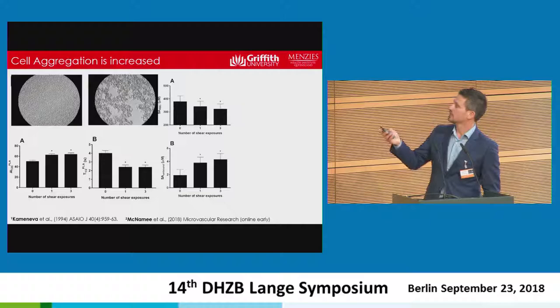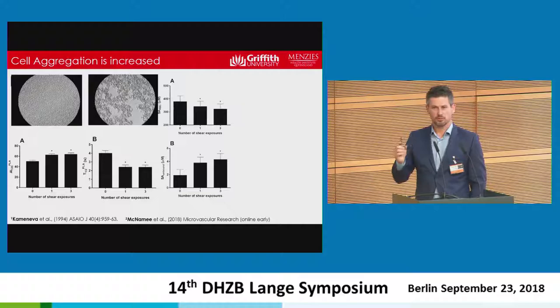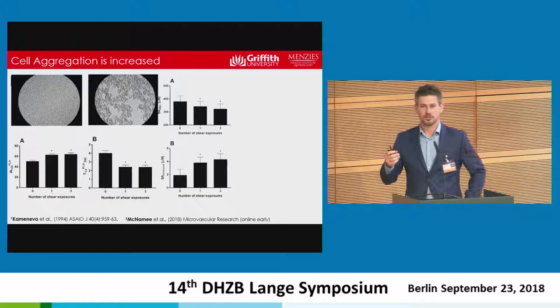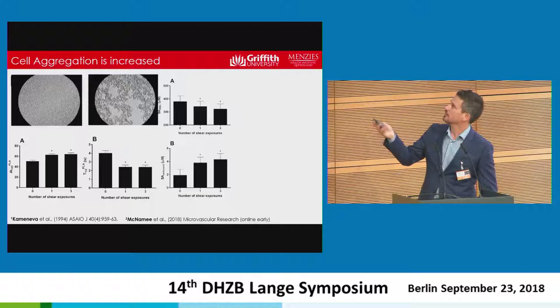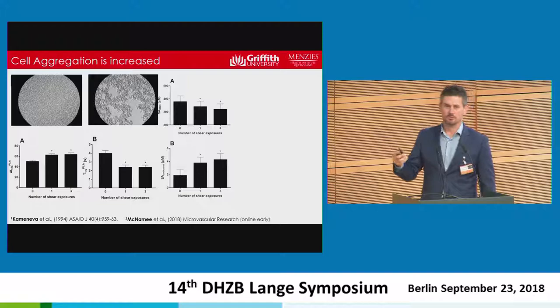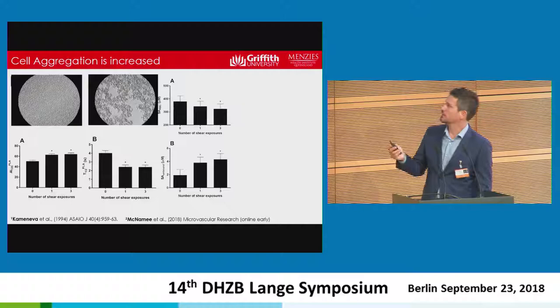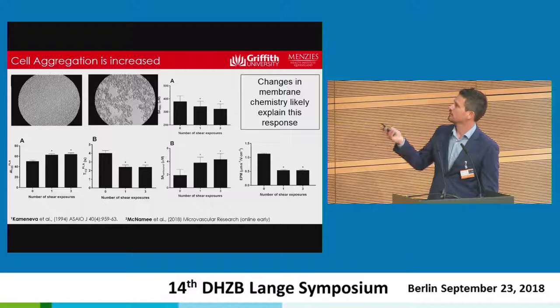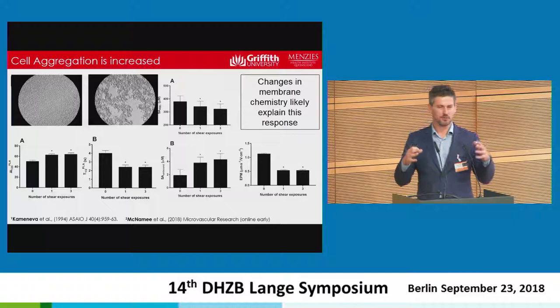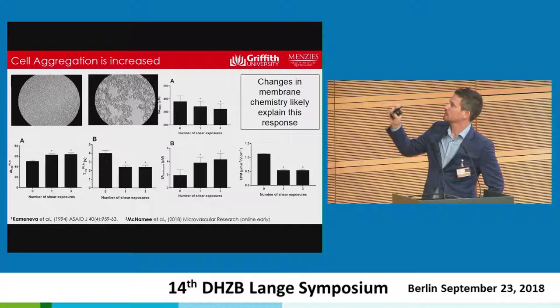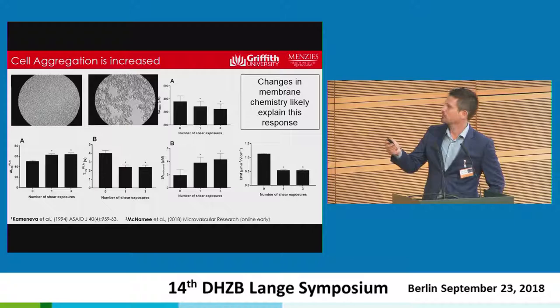We then looked at the surface chemistry of cells — specifically the amount of sialic acid, an important glycoprotein on the cell membrane that gives the cell its negative charge. Typically erythrocytes have a negative charge so they repel each other and resist aggregation. A single exposure to a high shear region decreased sialic acid on the cell membrane in a stepwise manner with each pass, and free sialic acid in the plasma increased correspondingly. Functionally, measuring electrophoretic mobility showed the cell had a reduced negative charge and was less able to repel. This surface chemistry likely explains why blood is hyper-aggregable and therefore hyperviscous in bypass.